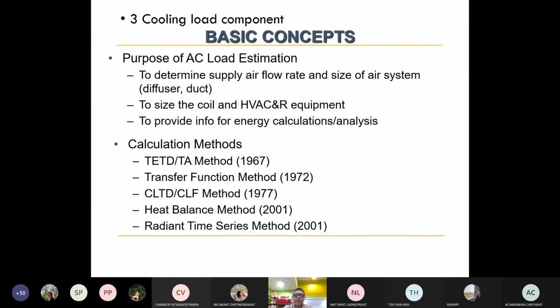We need to do the AC load estimation. Why do we need load estimation? Because when you do the load estimation, you can determine the airflow and the size of the air system, especially the diffuser or ductwork. You have to size the coil as per the HVAC and R equipment or the air handling unit, or the air conditioning. This can also provide information for energy calculation or analysis.